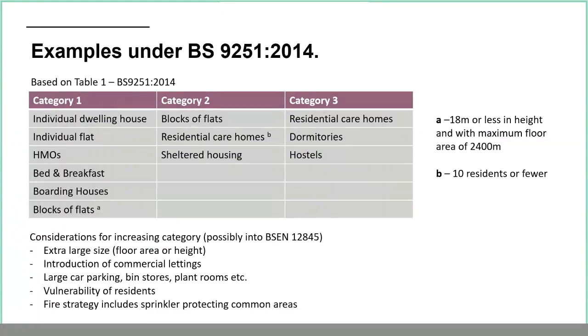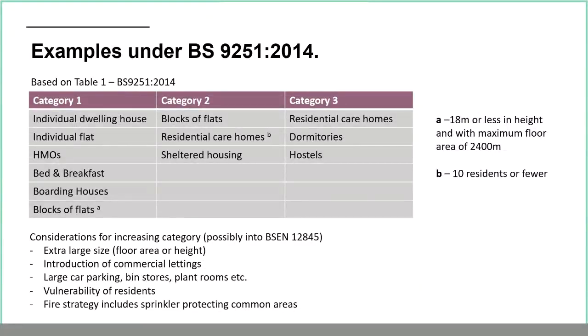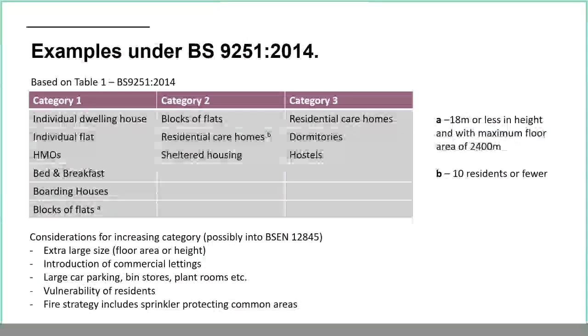Switching now to residential and domestic. BS 9251:2014 is currently the latest edition, though a new standard is coming. It is split into three categories found in table one. Some occupancies appear in more than one category — for example, blocks of flats appear in categories one and two, but could move to category three if there are vulnerable residents or other reasons to increase the classification.